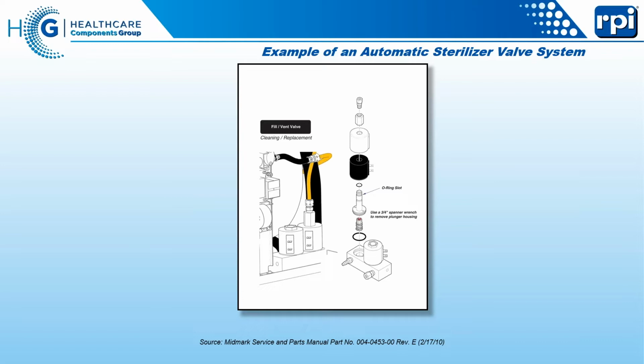On the other side, this is a normally open valve, and when we want to start building up pressure within the chamber, we have to electrically close this valve, and that will allow the pressure to build up. That way, if something happens to the electricity in this machine, this valve will automatically drop and you will never leave pressure in the chamber, supposedly. More on that later. But that's why this is a normally open valve, so that this machine cannot lock up like that.